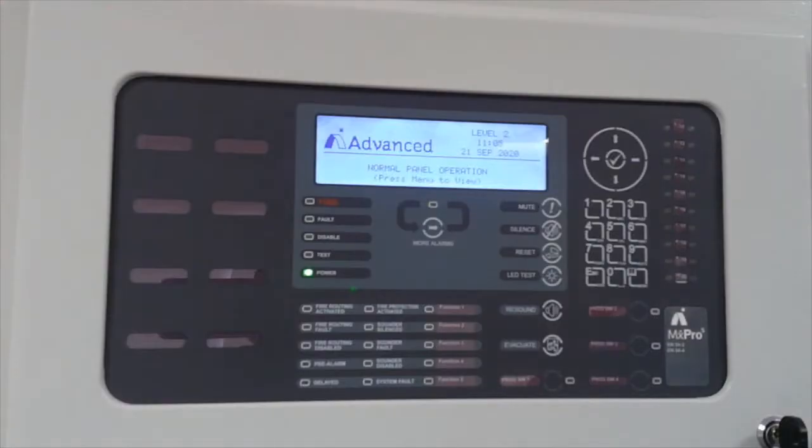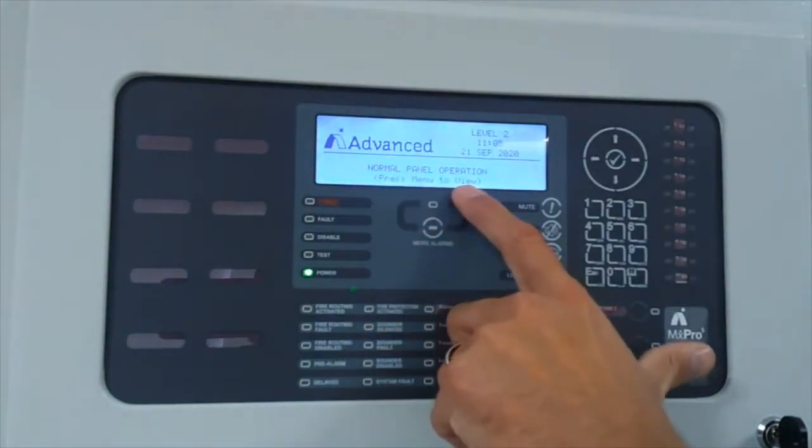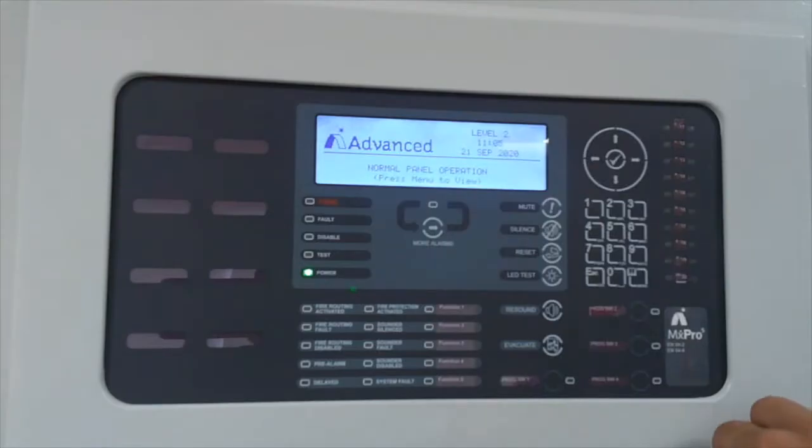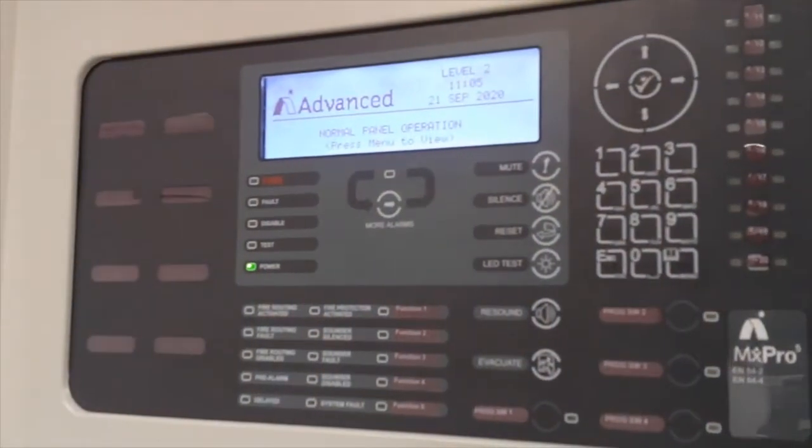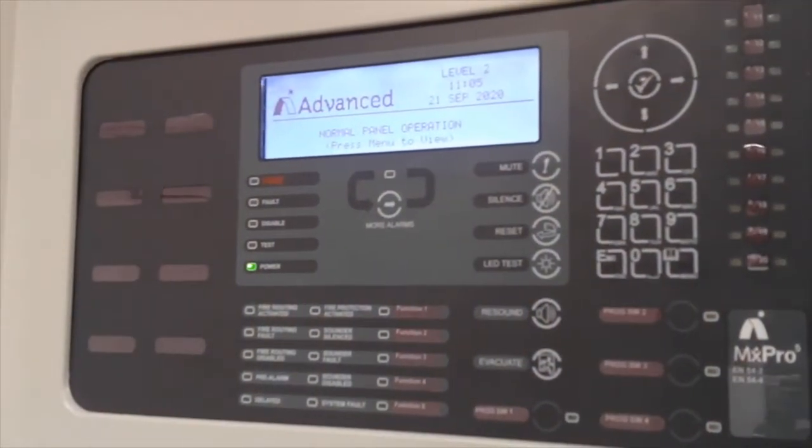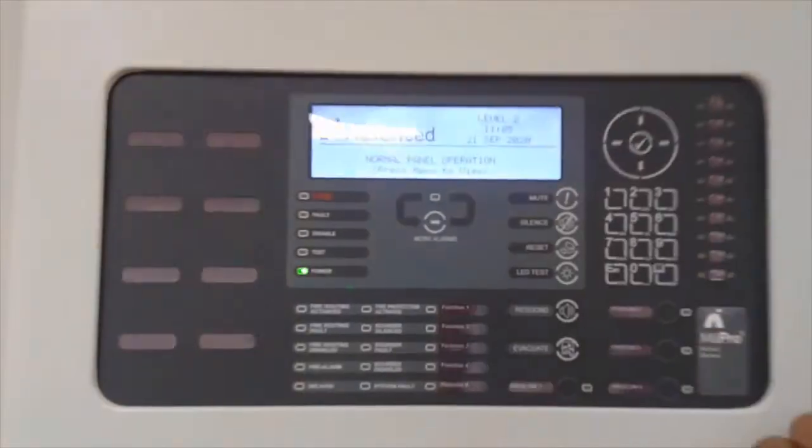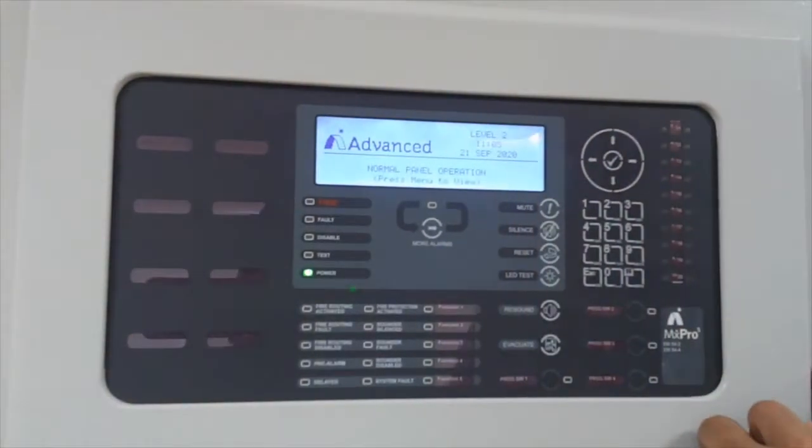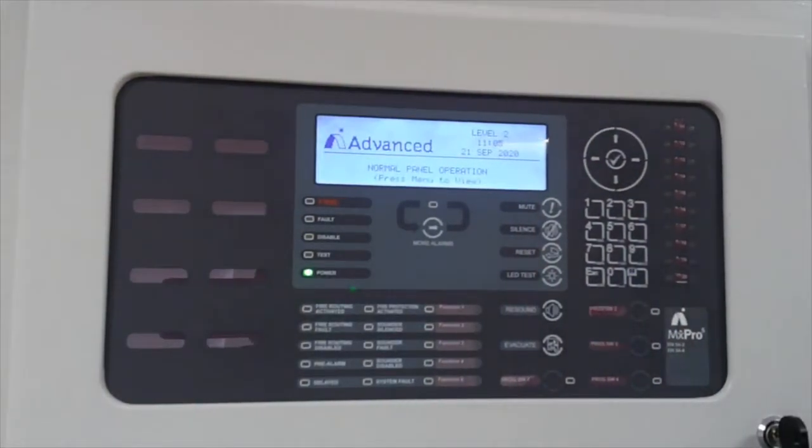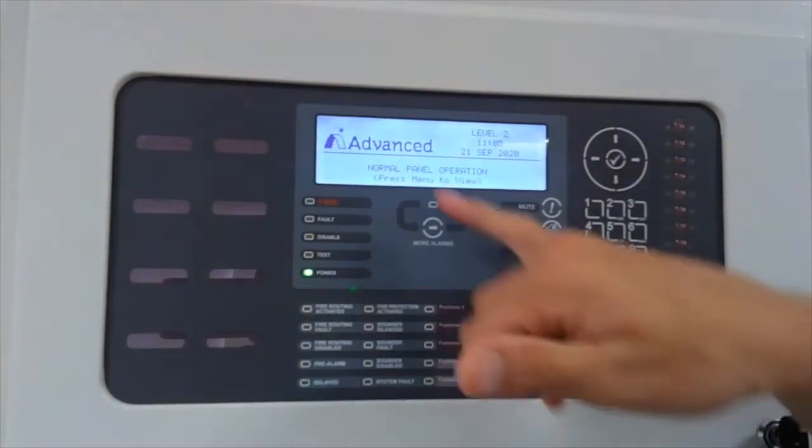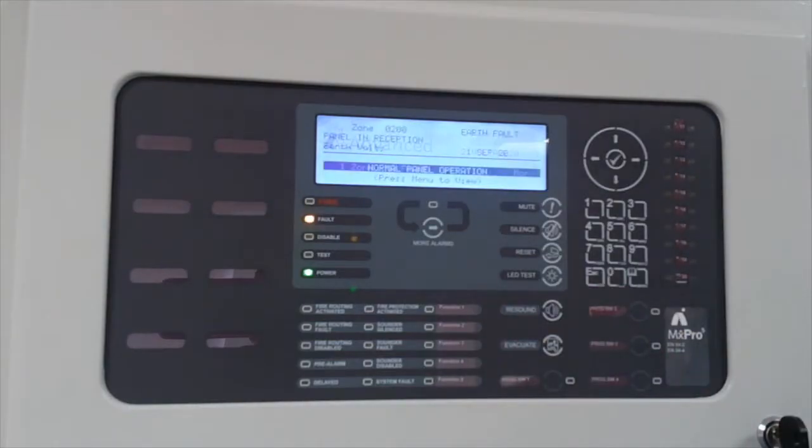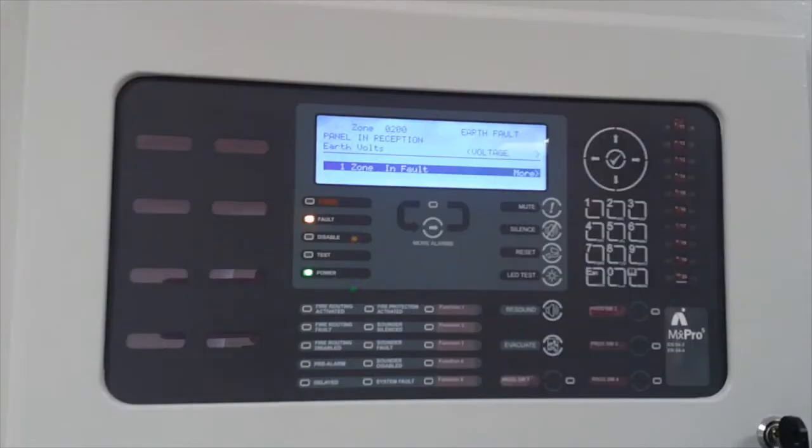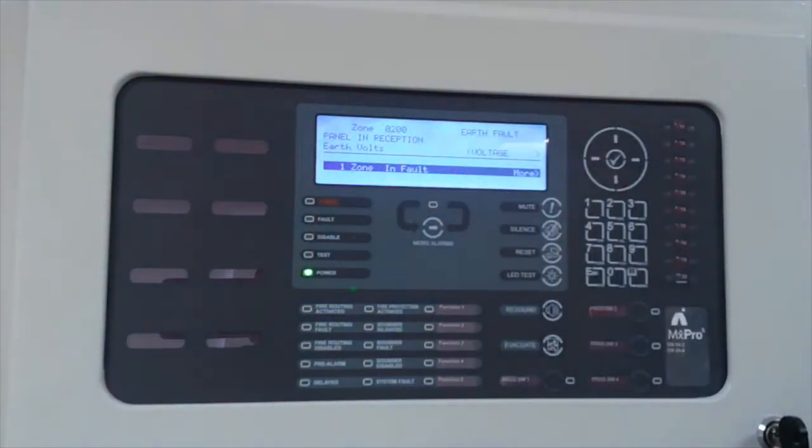Right guys, we all like to see a control panel displaying normal panel operation - this is ideal. However, in the unlikely event you do have an earth fault on the system, then obviously that display will change. So we can see normal panel operation, your earth fault's occurred, the panel is at level 2 menu so obviously it will buzz in a fault condition, but you can read the display.